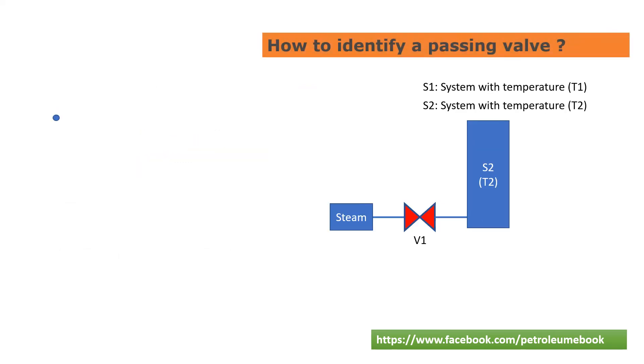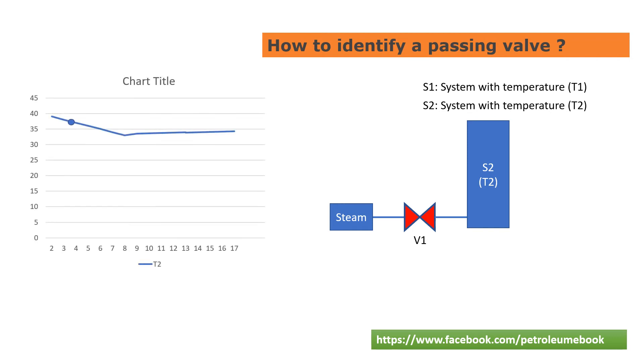The second example with the upstream system is steam. With the steam system, the pressure and temperature almost keep stable. We can confirm valve V1 passing by the temperature of downstream system T2. After fully closing V1, the temperature will firstly reduce, but after stopping steam a long time, if temperature T2 increases again day by day, we can conclude that valve V1 is passing.